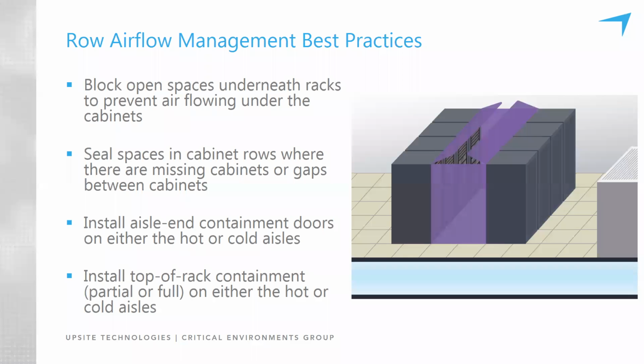The second is sealing open spaces in the cabinet rows. Depending on site conditions, some layouts will end up with gaps between the racks due to support structures, other types of barriers in the room, or intentional space that's been left there for a future roll-in rack. Installing aisle end doors prevents the wraparound mixing that will occur at the aisle ends if doors are not used. Doors are very important, and they're available in many designs from a variety of manufacturers, and we'll get into greater detail about doors on some of the subsequent slides.